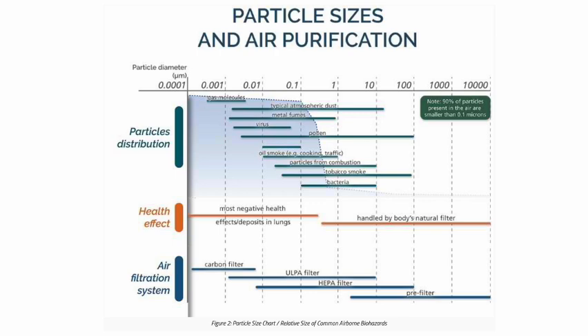Okay? So what is the difference between them? The two filters have different filtering capacity when it comes to the size of the particles they can filter. Usually the smallest organisms that it can filter are viruses. In terms of viruses, the HEPA can only cover about half of the size of your viruses, so it does not cover the smallest viruses. But the ultra low penetration air filter can cover the entire size band of viruses. Thus, your ultra filter gives an edge in protecting the user and environment.